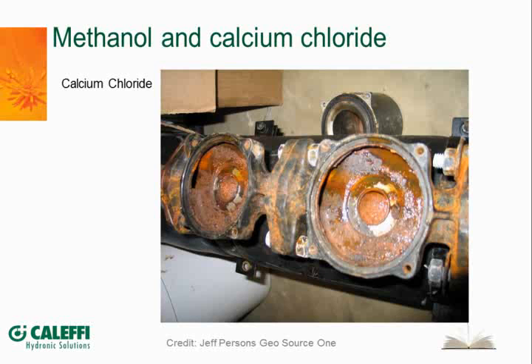It's an unfortunate circumstance. A second subcontractor, in the process of replacing equipment, opened the loop and decided he'd prefer to work with an open flow center. He did not realize there was calcium chloride in the original system; it was just a clear fluid, and he topped it off with methanol to increase the antifreeze strength of the system. So now he had calcium chloride, which is corrosive by its own nature and becomes extremely aggressive with oxygen contact, combined with methanol in an atmospheric flow center at the same time.